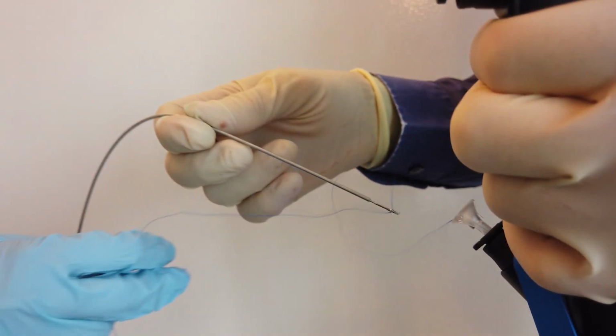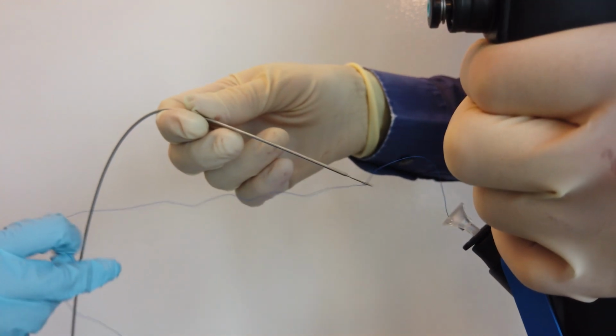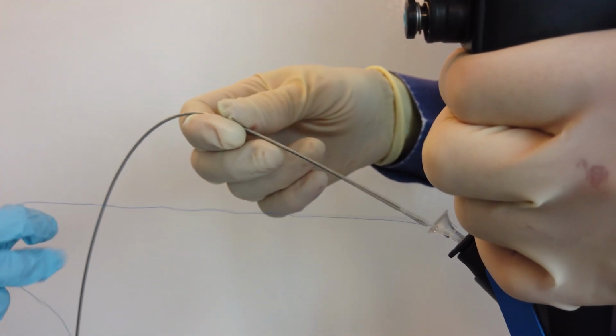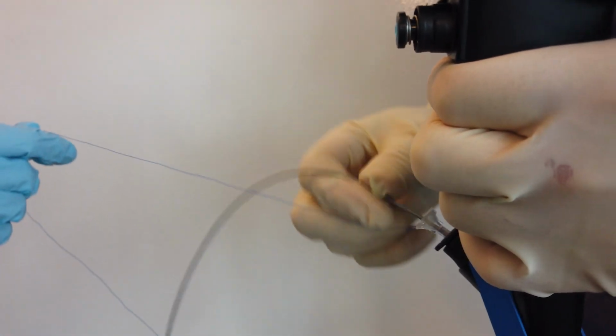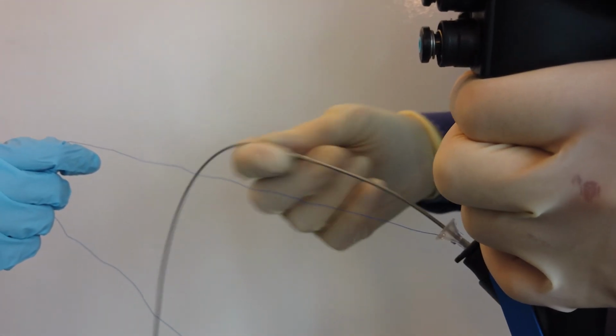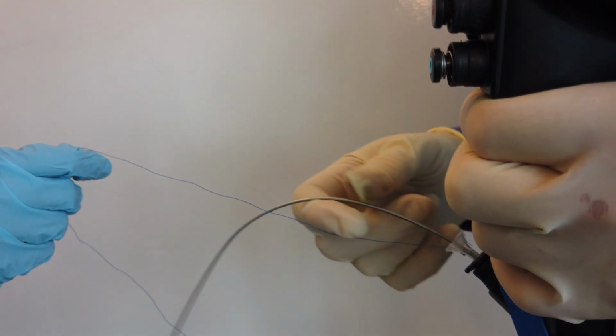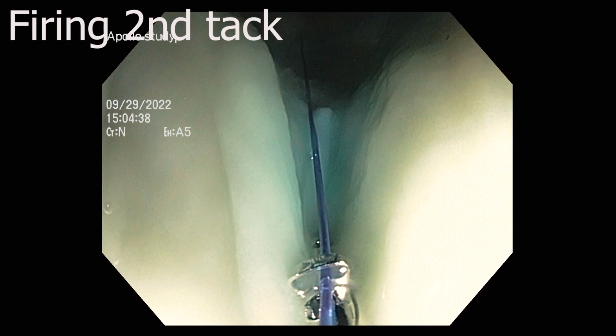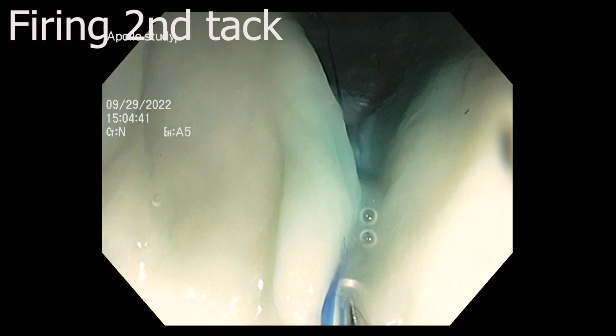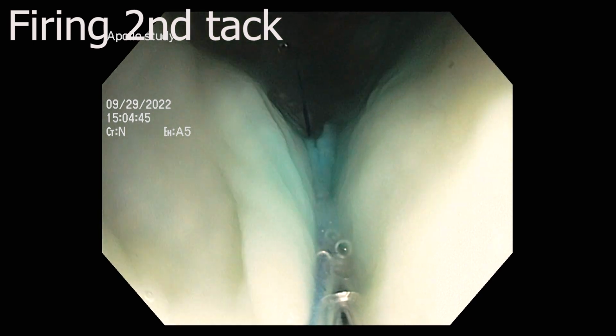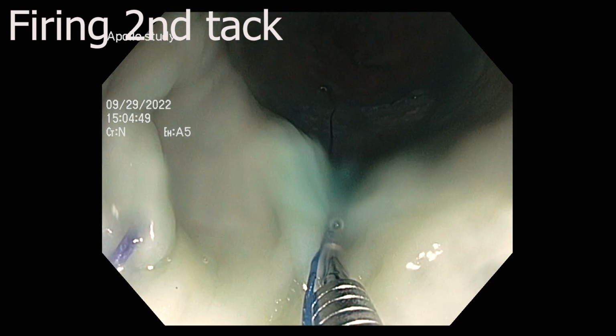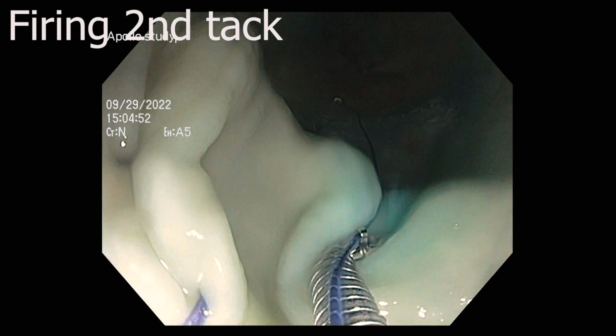The loaded delivery device and tack are then pushed through and beyond the loading sheath and the tack card. The loaded delivery device is then reinserted. The assistant should hold the external end of the suture steady during insertion to prevent the suture from getting pulled into the scope. If extra suture is pushed into the channel, it can lead to tangling, mid-suture knot formation, and device failure. Once fully inserted, the delivery device and tack are positioned, forward pressure applied, and the handle closed, which inserts the tack.